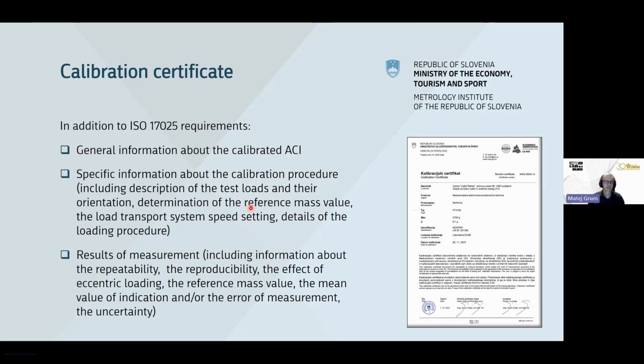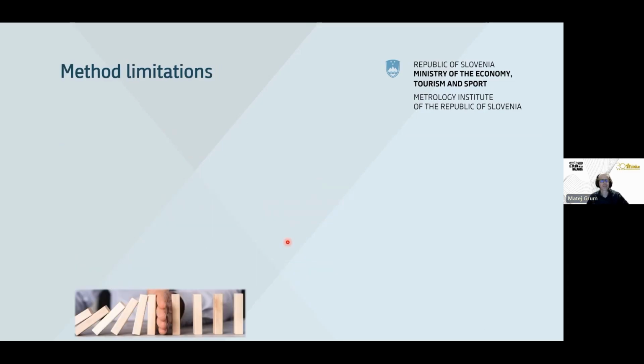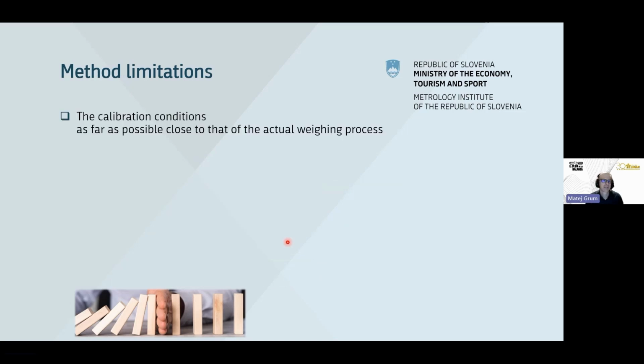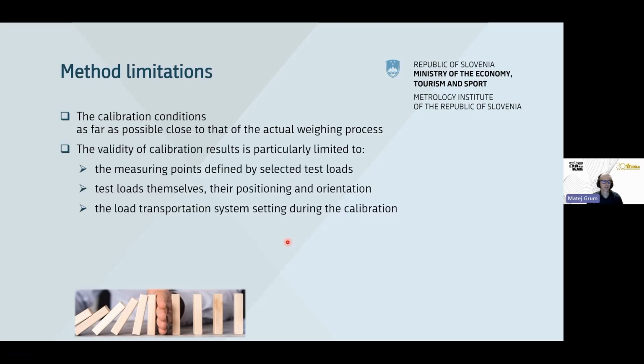Further, it is defined which results need to be reported in the certificate. Of course, information about repeatability, reproducibility, the effect of eccentric loading, the reference mass value, and finally the mean value of indication with the error of measurement and the uncertainty of calibration. Already during the presentation, I mentioned that there are some important limitations to the method. It is important that calibration conditions are as far as possible close to those of the actual weighing process. Any change of the calibration procedure can bring a different response of the instrument and can invalidate the results which are reported in the certificate.